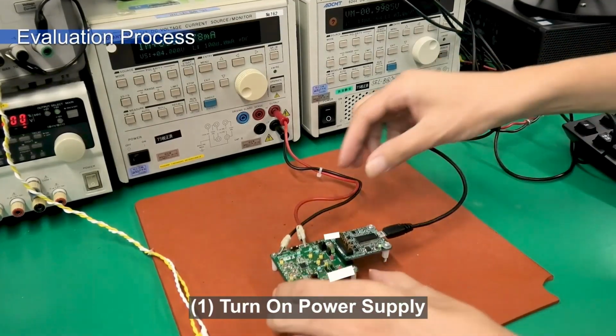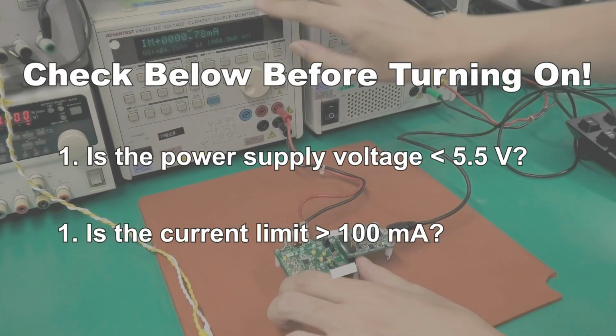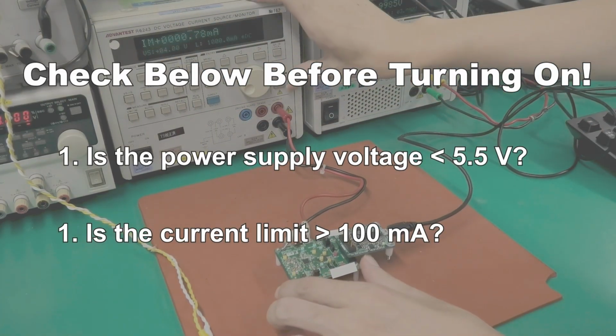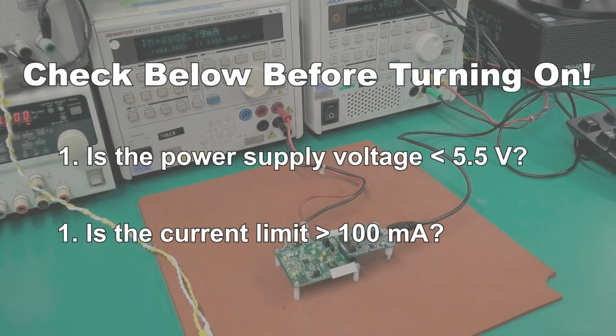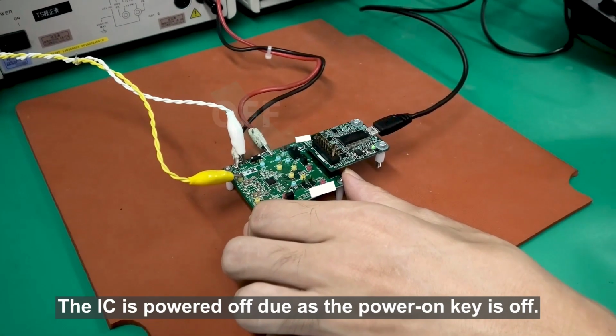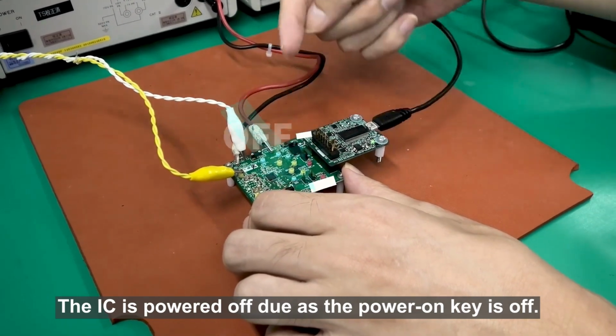Turn on the power supply. Please make sure to limit the power supply voltage. The voltage should be less than 5.5 volts. For the current limit, please set it to more than 100 milliamperes because more than 100 milliampere current is required as a startup current. There is a power on switch on the evaluation board.